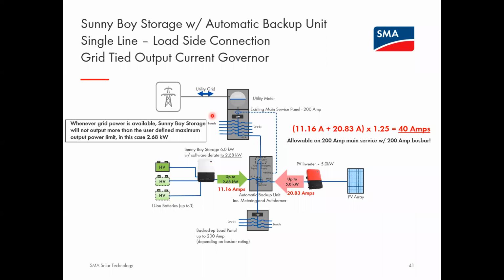So here's what I mean. Again, to take that example where I'm connected to the load side of the main service, my automatic backup unit's here. Also assume that I have a 5 kilowatt PV inverter, which outputs 20.83 amps. Using this governor feature inside the SunnyBoy Storage, I can software derate the nameplate power rating of this inverter from, let's say, 6 kilowatts down to 2.68 kilowatts, just by changing a setting within the inverter software.